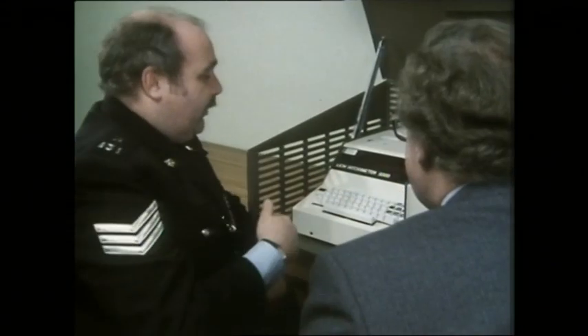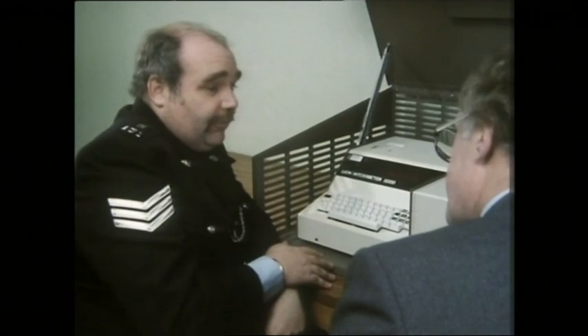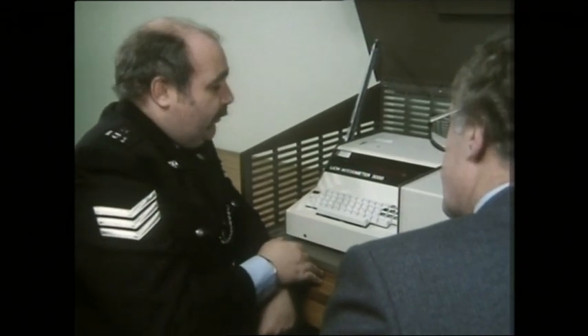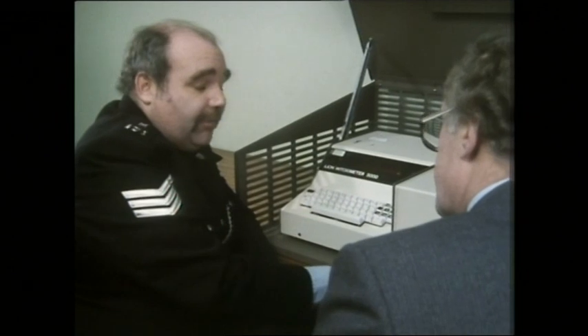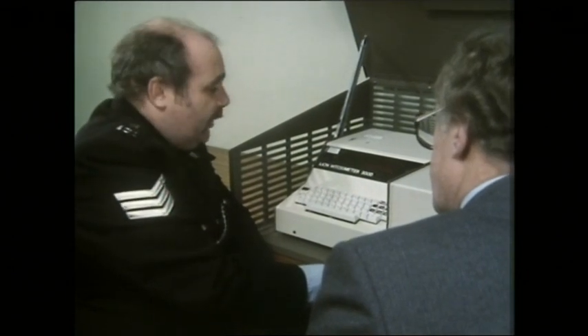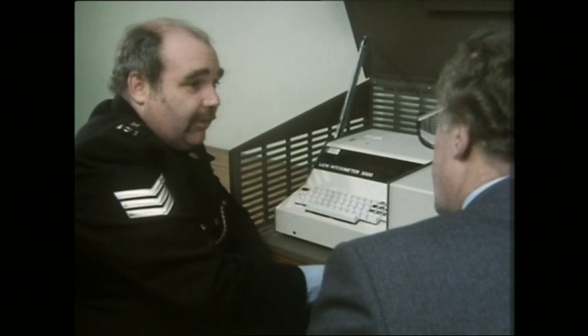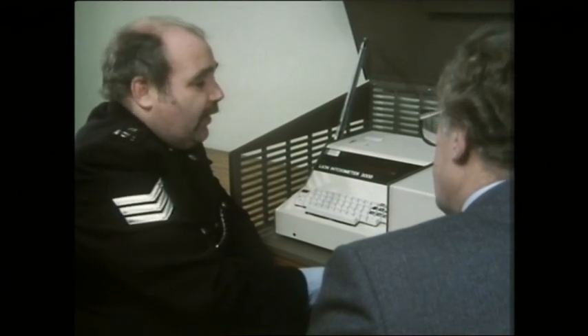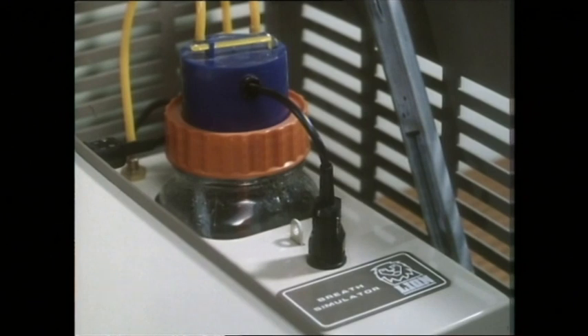Only an authorised police officer can perform the test, and all the information he enters into the machine is necessary to be certain that the printed output is acceptable as evidence in court. First of all, it's purging out any contaminants that may be in the analysing compartment. And it will then check to make sure that the machine is recording 0. Then it will use the simulator over there to check its own calibration by taking vapour from a known quantity of alcohol. Now the machine has reported that that calibration is OK. It's now purging that out of the system.